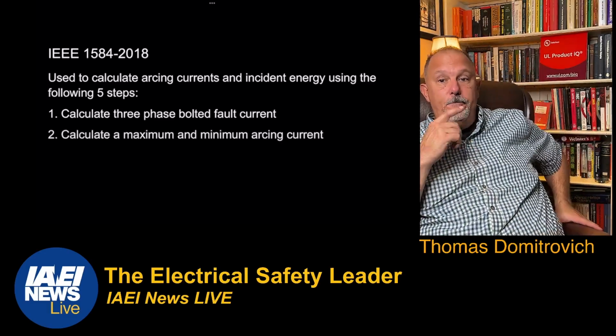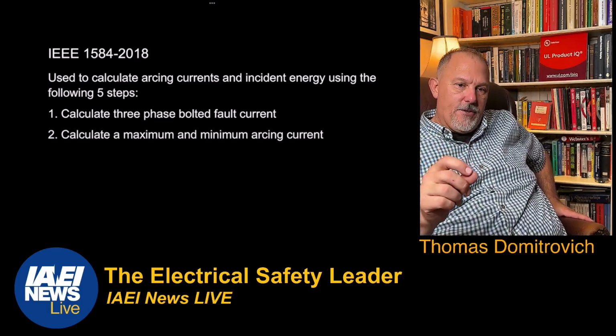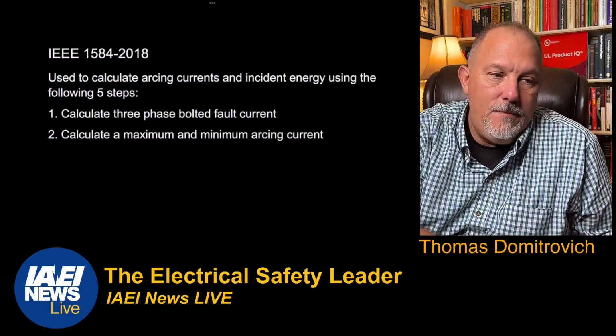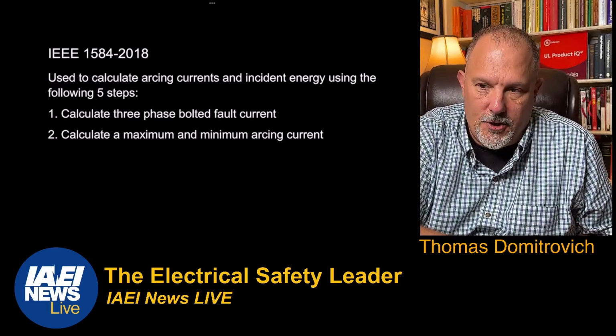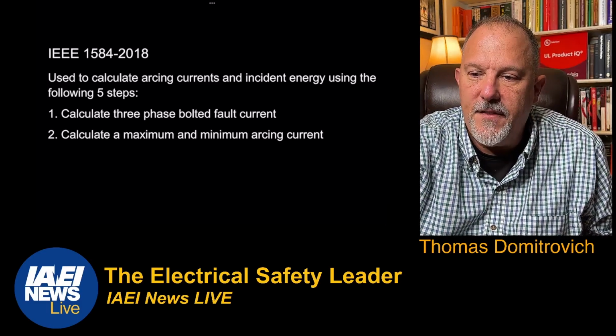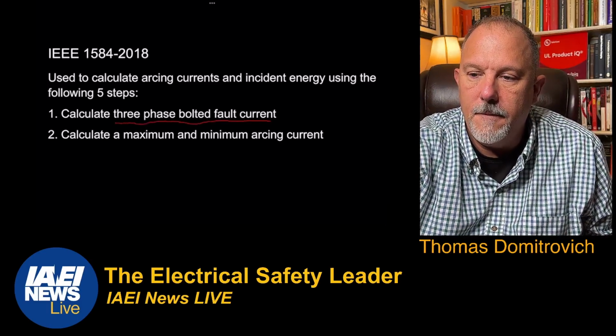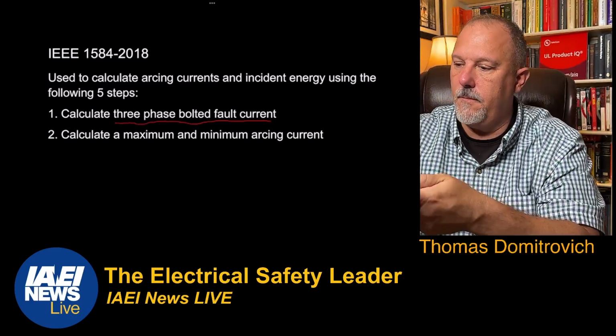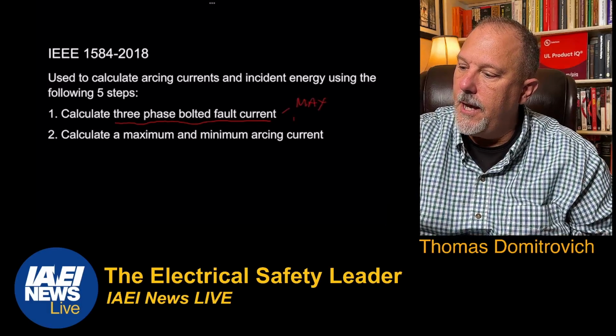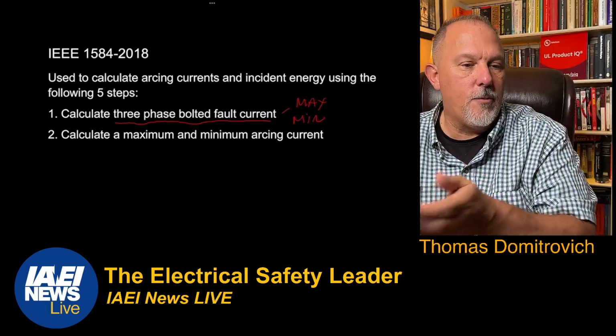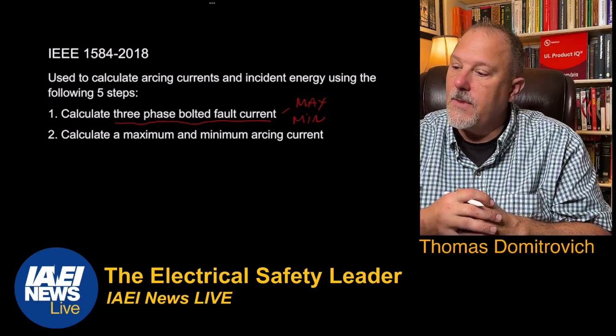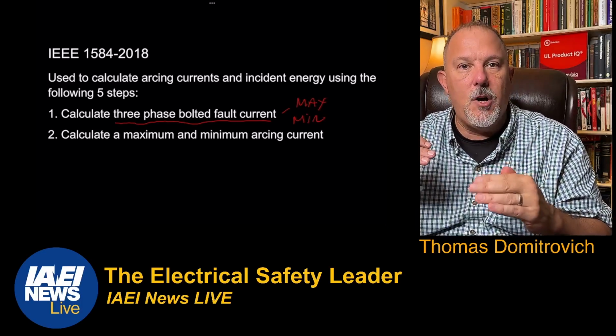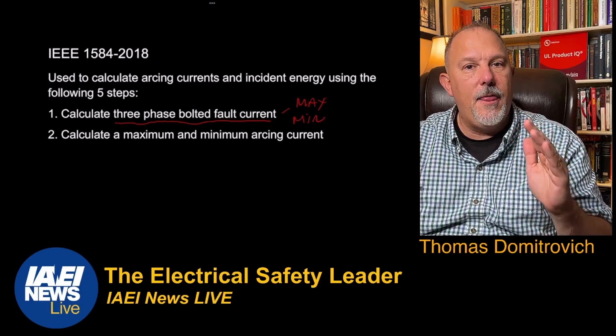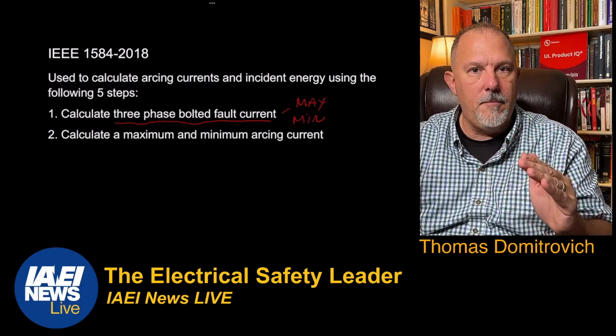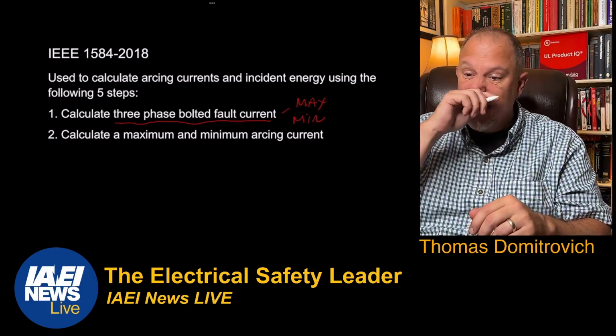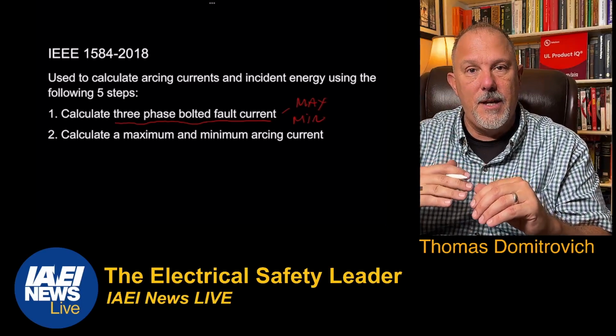Second, we need to calculate maximum and minimum arcing currents. Now, in reality, I may calculate the maximum and minimum bolted fault current values as well. I'm going to put that in here: 3-phase bolted fault current values, right? And we're going to say max and min. The reason that's important is because I need to calculate maximum and minimum arcing fault values, because the maximum or minimum could yield the highest incident energy.